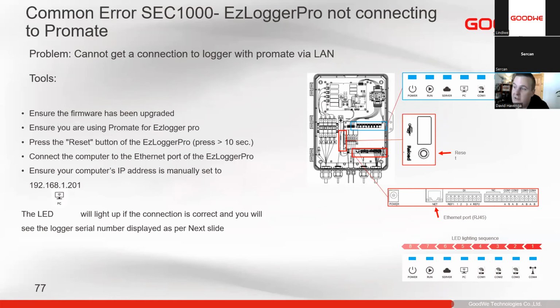So we ensure that the firmware is updated. For the newer ones, we don't really have to worry that much about firmware. All the newer loggers we get now should all have the latest firmware on them. We connect our laptops to the LAN port. We're then going to press the reset button. So these devices all come standard in DHCP mode, which makes it nice to plug it into a router and it's going to work. But we cannot configure it like that. So here on the side, we'll find a little reset button next to the USB port that can be used for firmware updates.